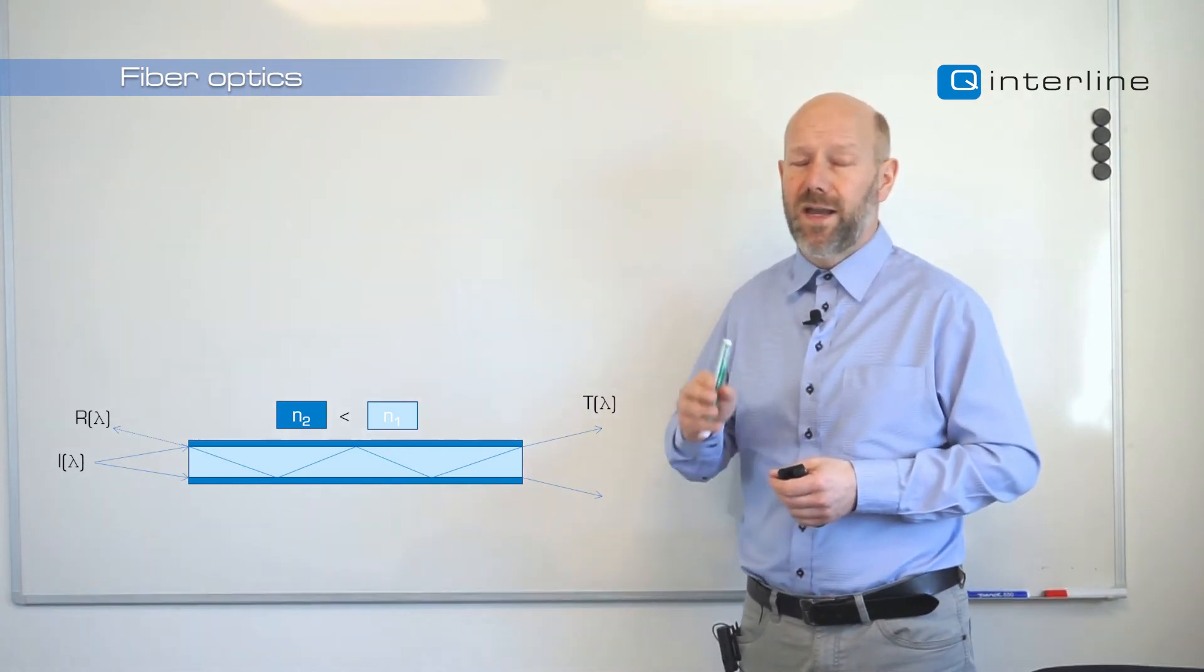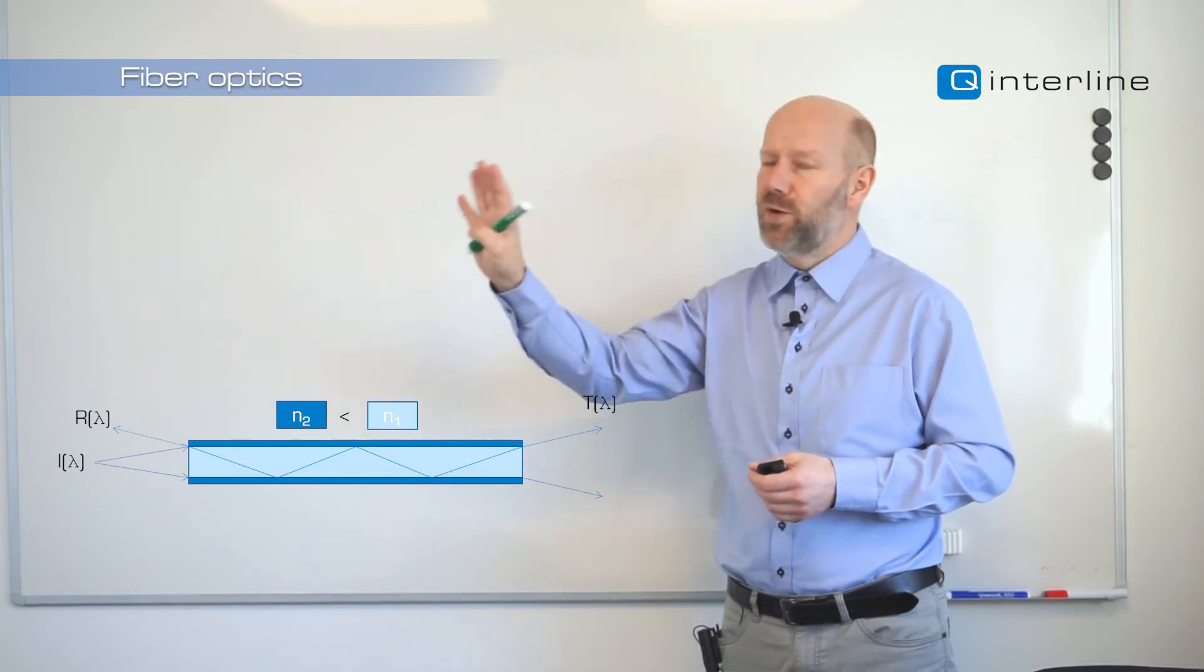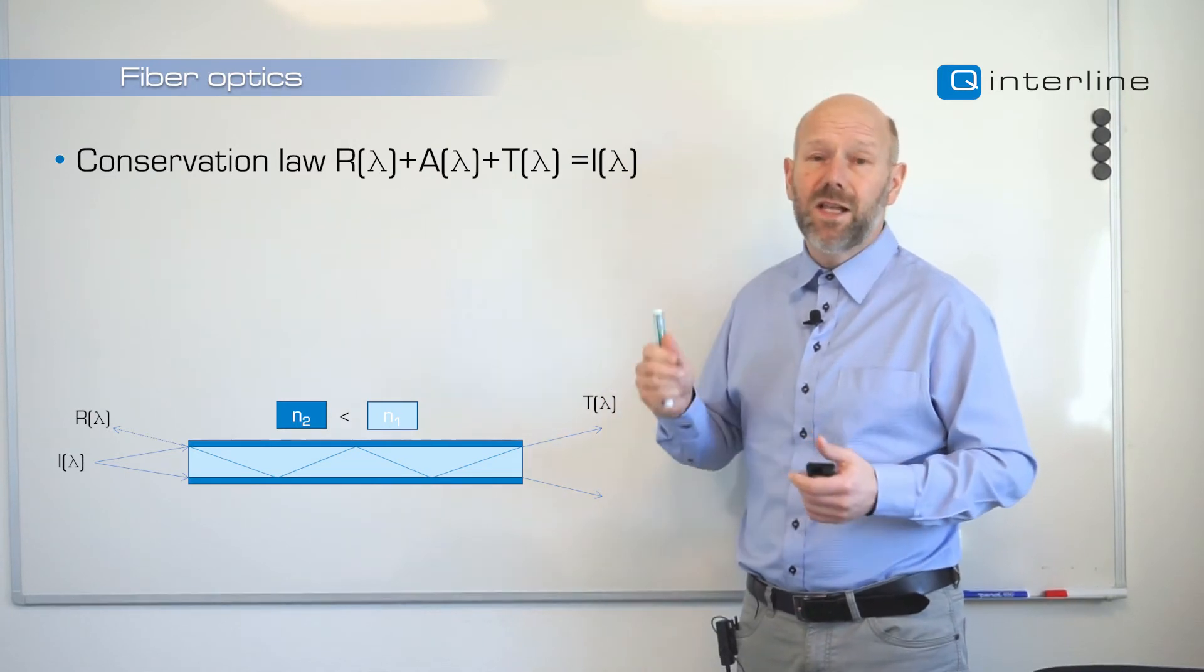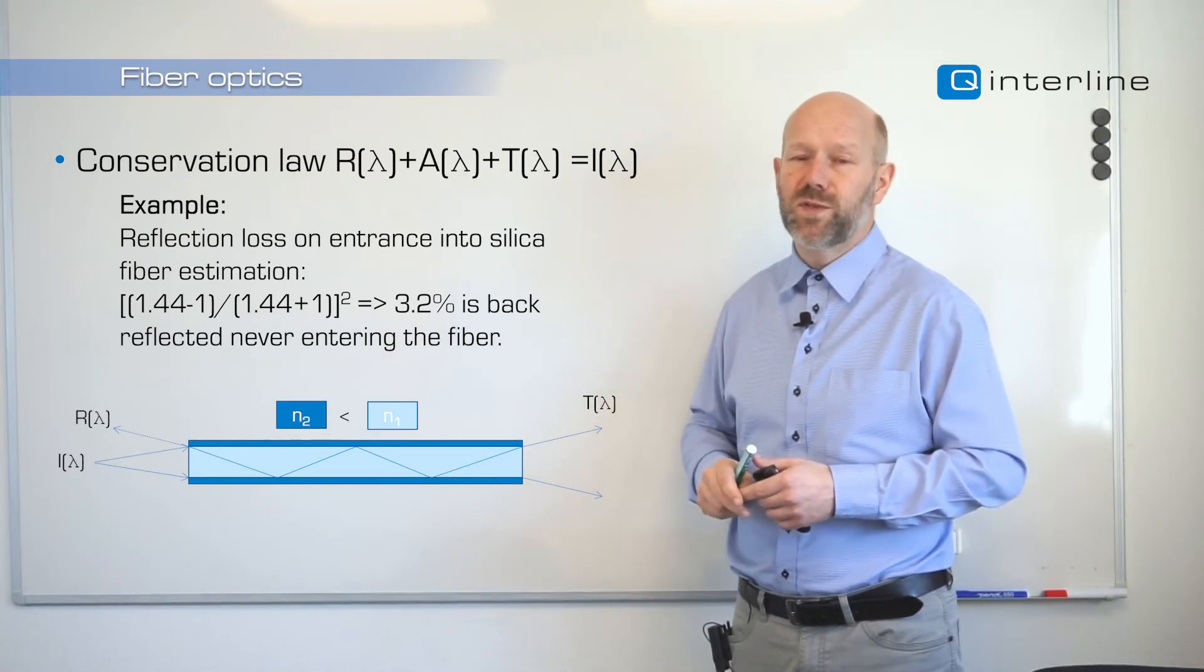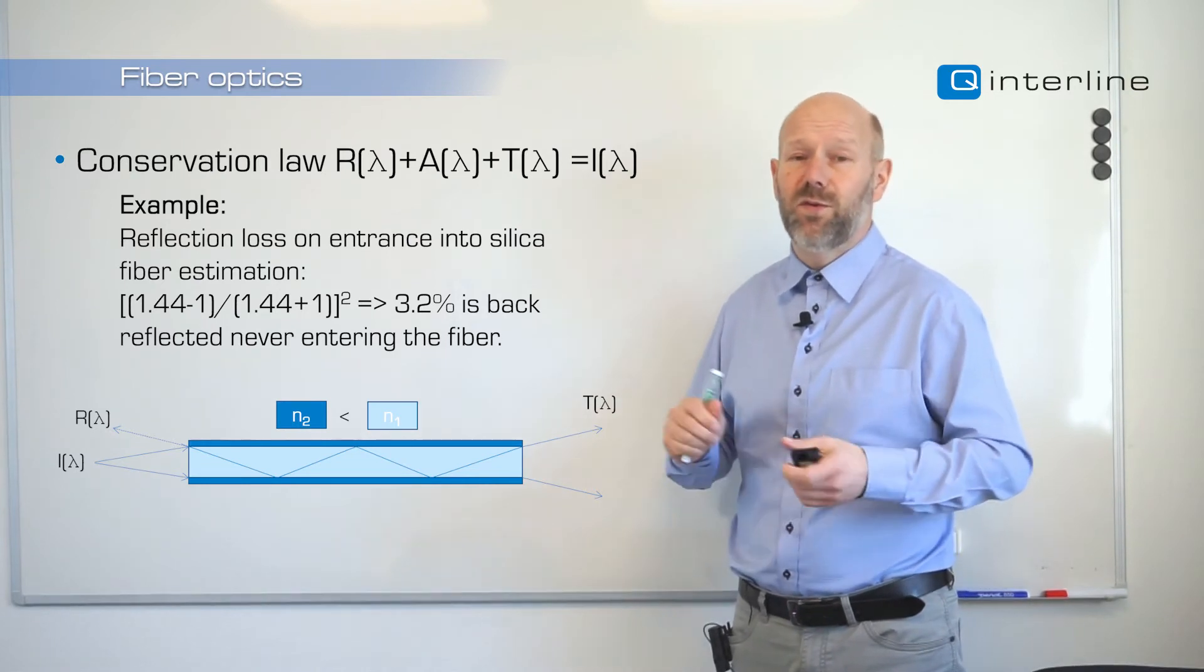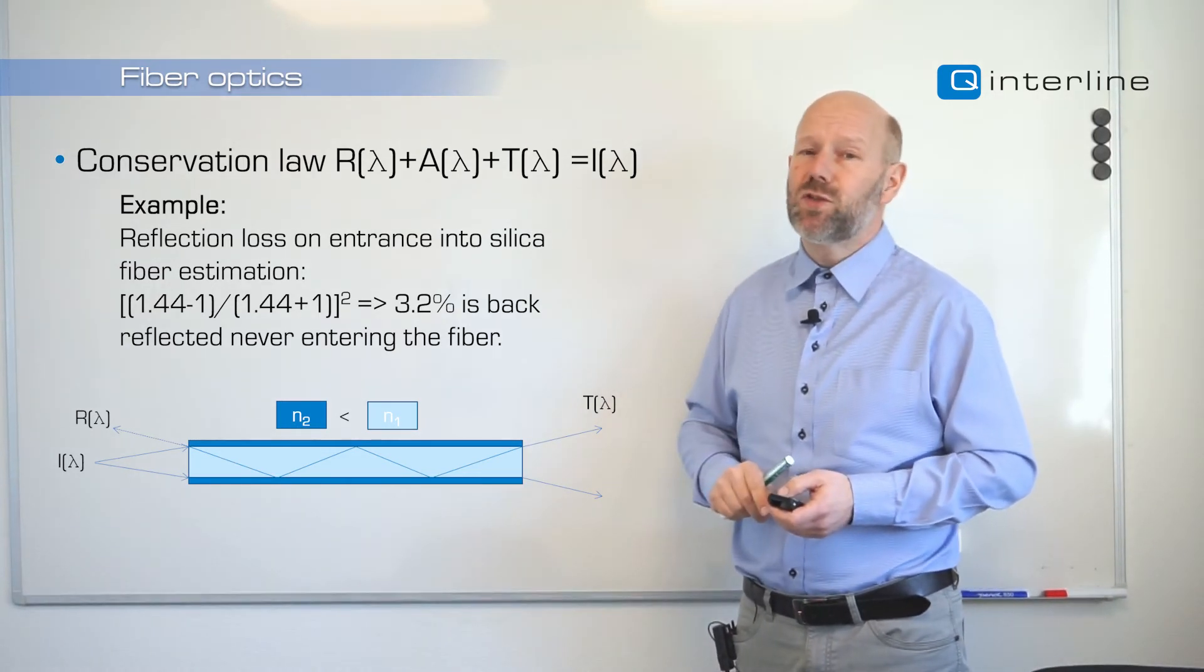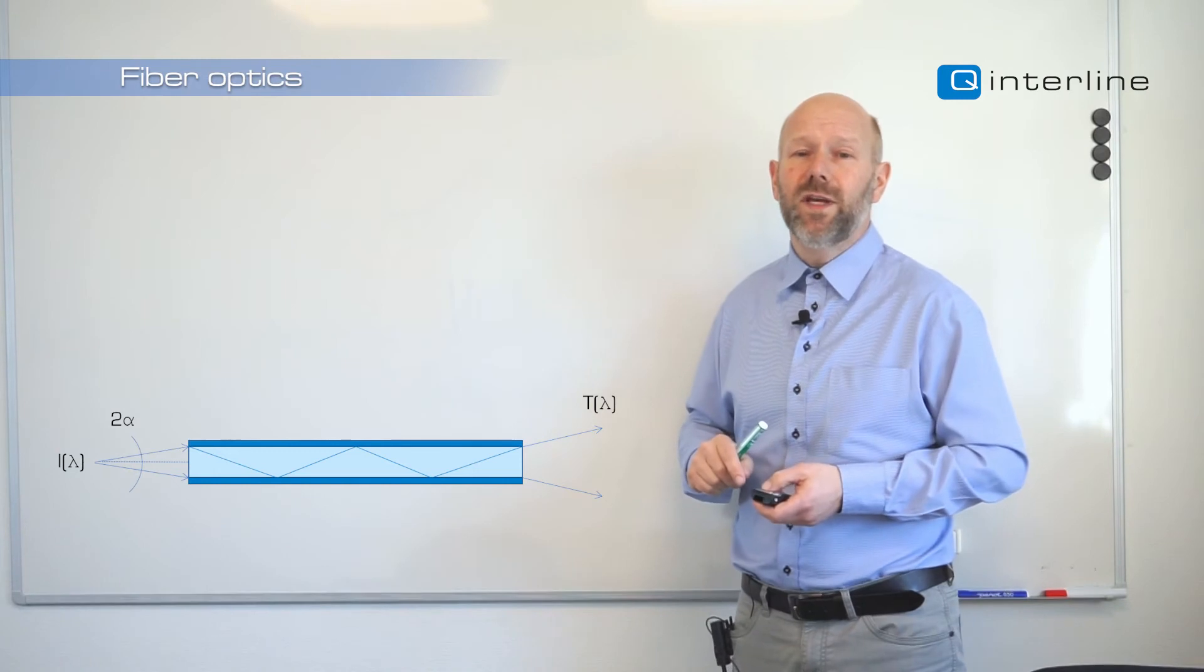Let's look at a few of the losses that will happen. They are either lost by reflection on the entrance, absorption in the fiber, then further on light will be absorbed by the sample. The reflection loss at the entrance can be estimated by this formula and if we calculate it we can see that roughly 3.2 percent of the light will never enter the fiber. So roughly 97 percent of the light enters the fiber but now it will be absorbed along the road. Not all wavelength will travel at the same easiness.